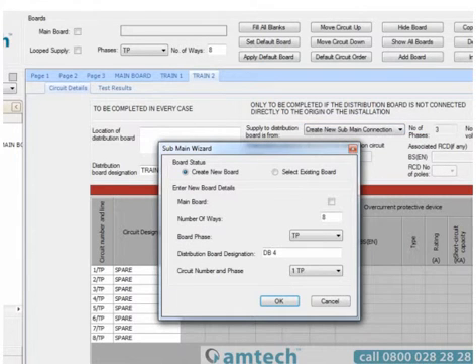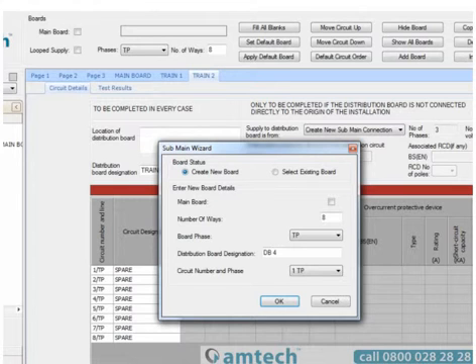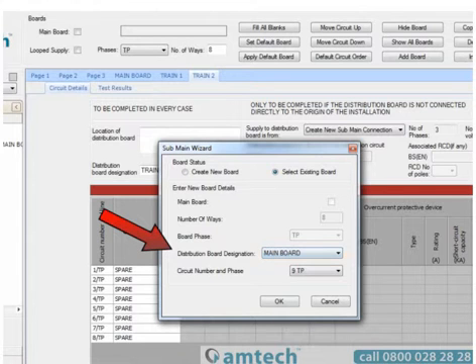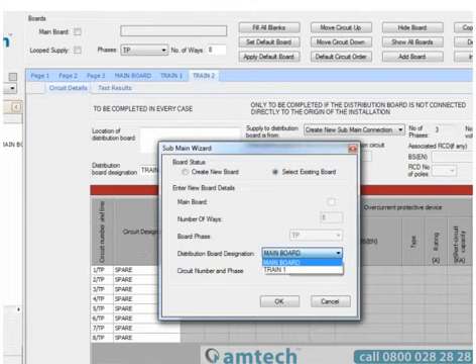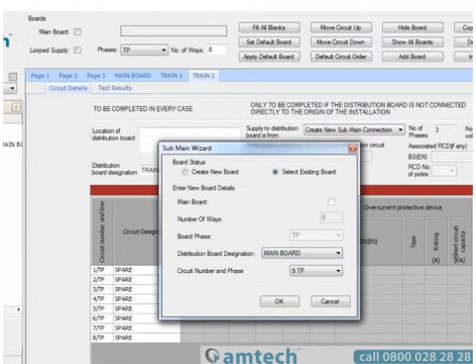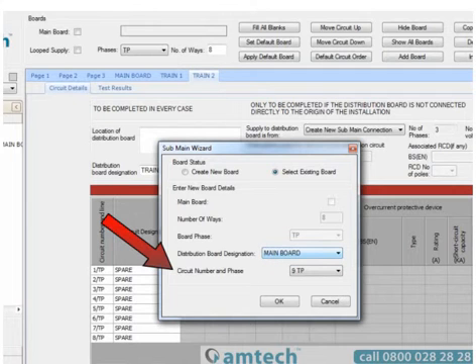In this sub-main wizard, we now have the option to create a new board or select an existing. As ours already exists, we're going to use this option. We can now choose which board we intend it to be supplied from. By using Distribution Board Designation drop-down, we can see all the boards available that have spare three-phase ways that can be used to connect this board. We're going to use the main board and then select the circuit number and phase we intend to connect it to.